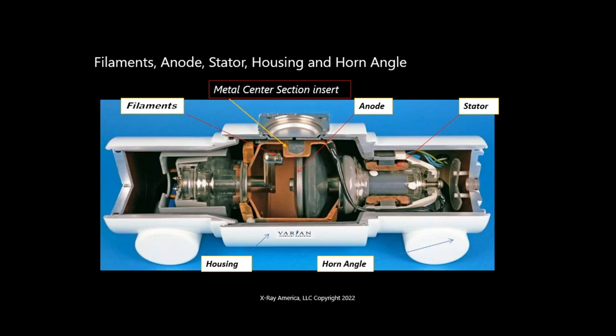The detail that you don't need to concern yourself with particularly is that the metal goes to ground. And so there's the bleed off, and extra tungsten from the filament is distributed evenly around that. You'll see what happens when you don't have it. So in it we have the housing.